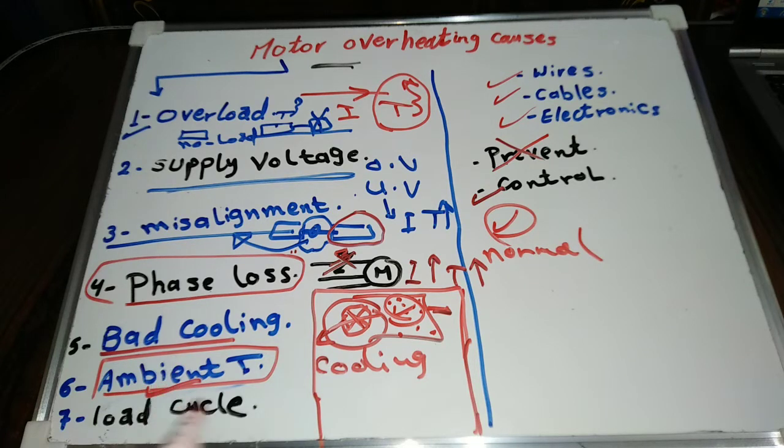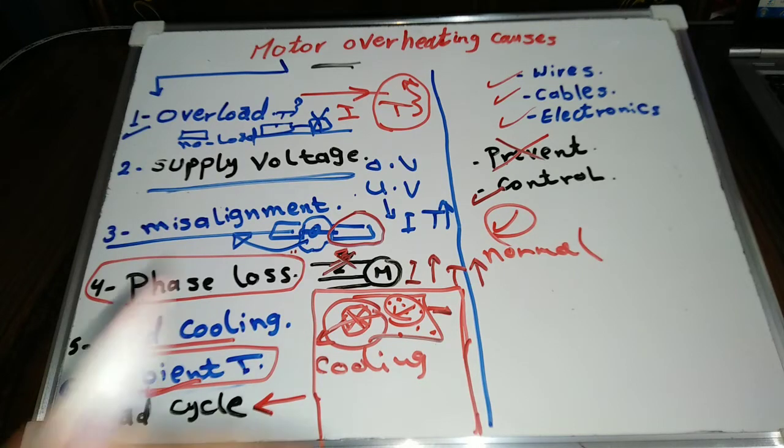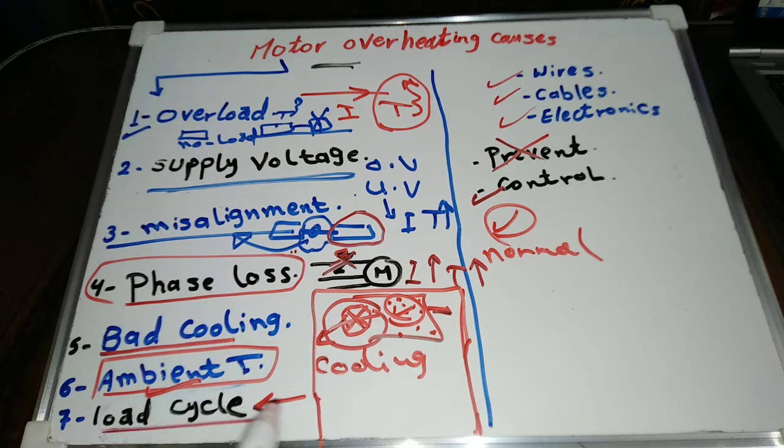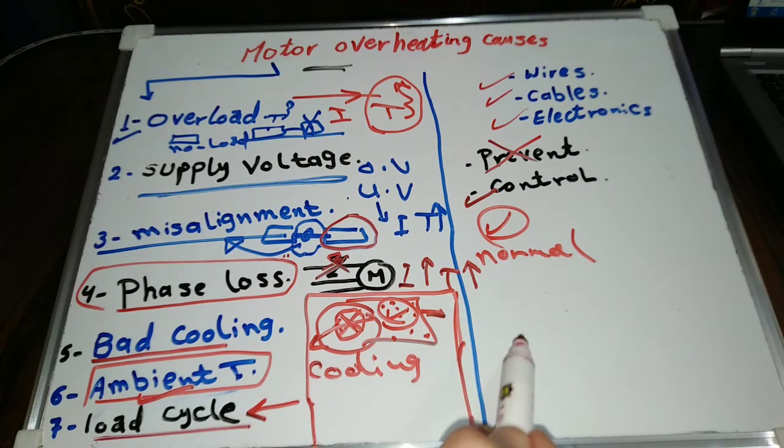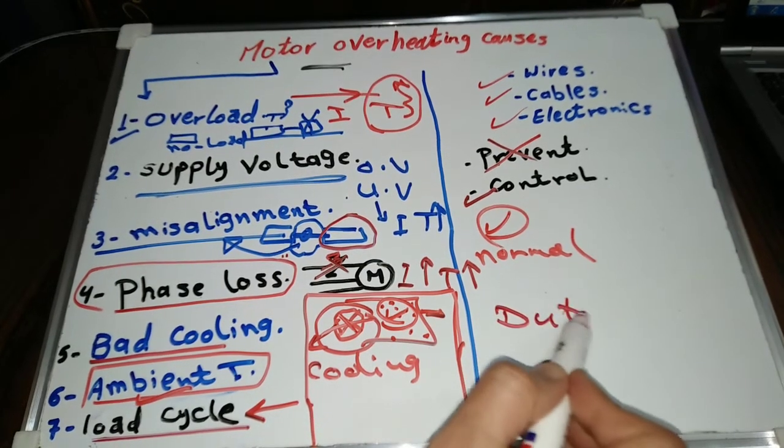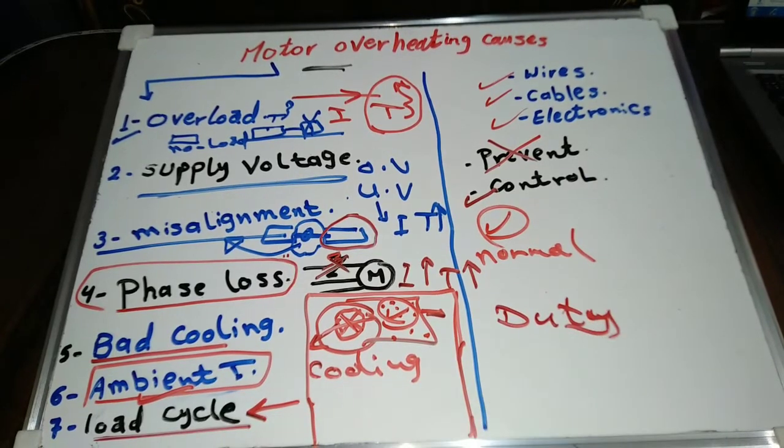Unsuitable motor for the load. If the motor power is suitable to the load, it's not enough to ensure that the motor will not overheat. Besides the motor power, you should take into account the load cycle or load duty cycle, which means the periods of the load.